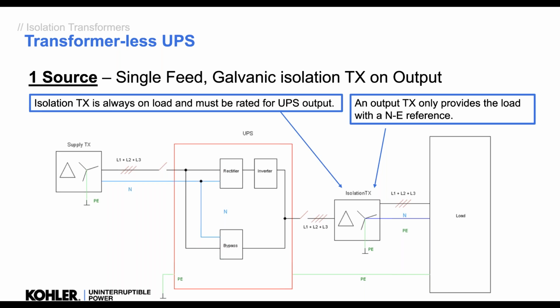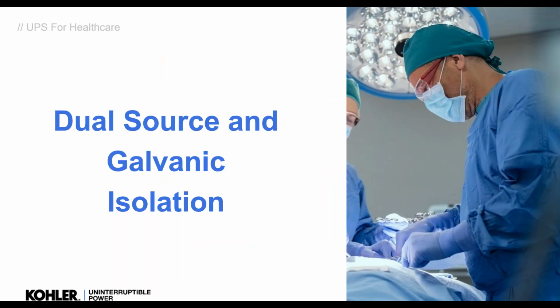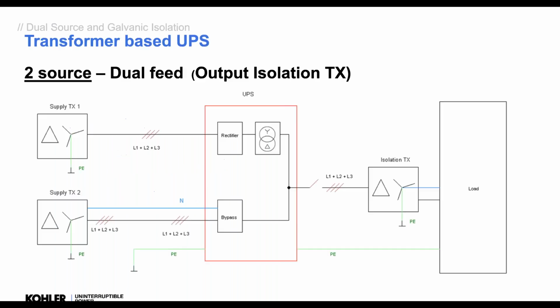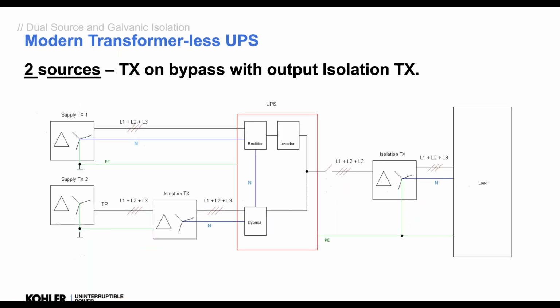when it's on the output, we do have to make sure it's rated for the output of the UPS or whatever protection we have. It is possible to put small isolation transformers spread around the property, so we have one big UPS and small transformers fed to local load, so we don't have to be in the same place. So I mean, it's worth having a discussion about how we're going to do this. So if we have dual source and we want galvanic isolation, we want to create a new neutral earth, how do we do that? Okay, so if it was an old transformer-based UPS, we would have two sources, one for the rectifier, one for the bypass, and an isolation transformer to create the output reference on the neutral. Okay.